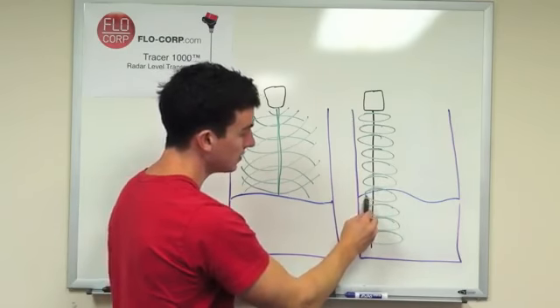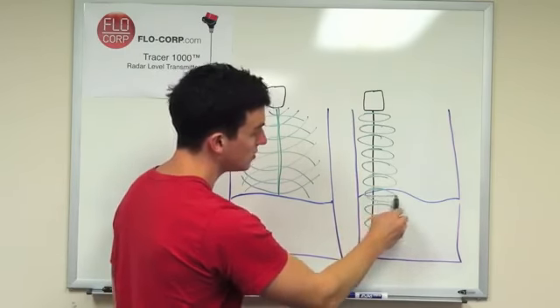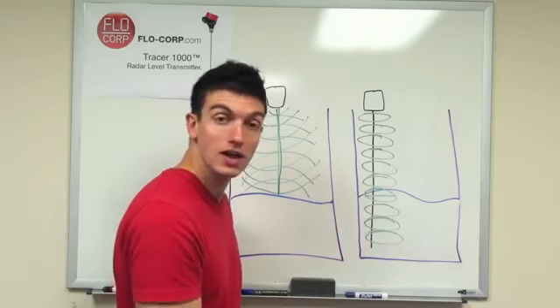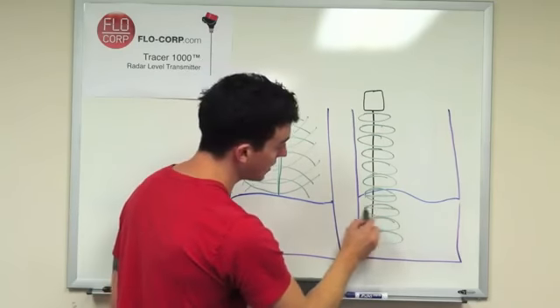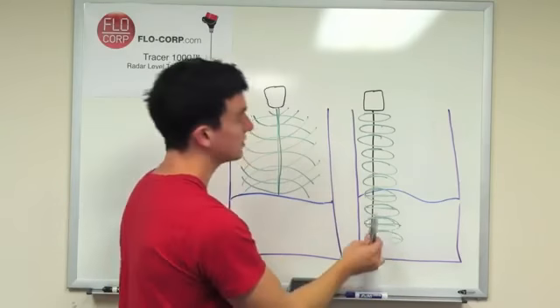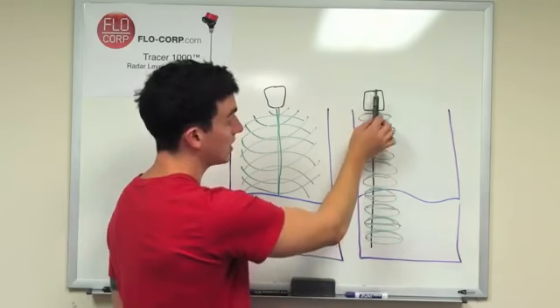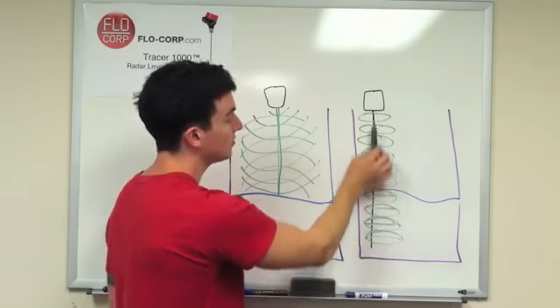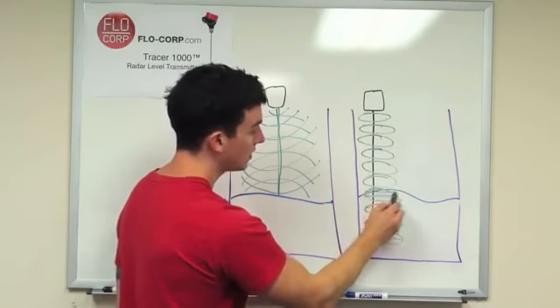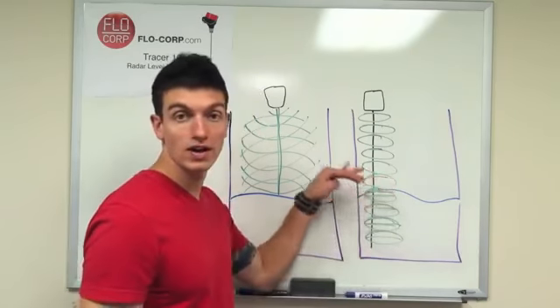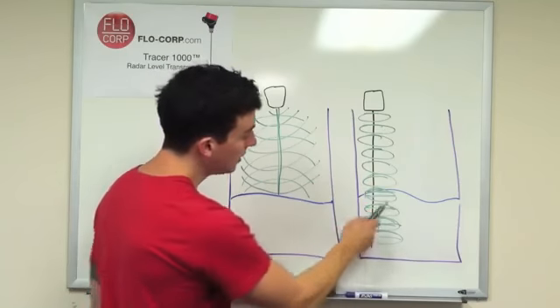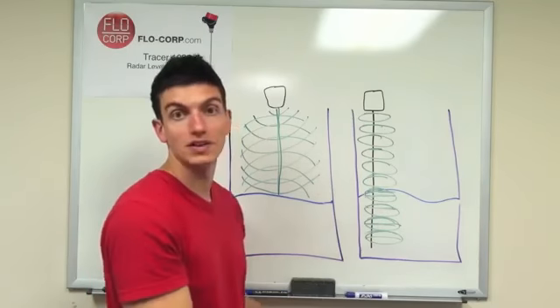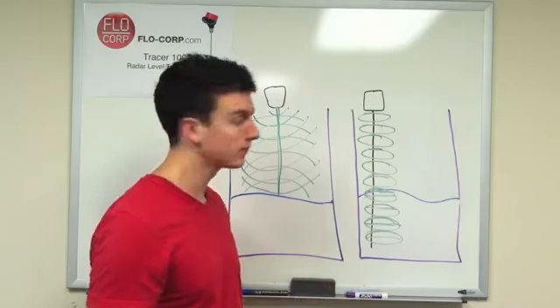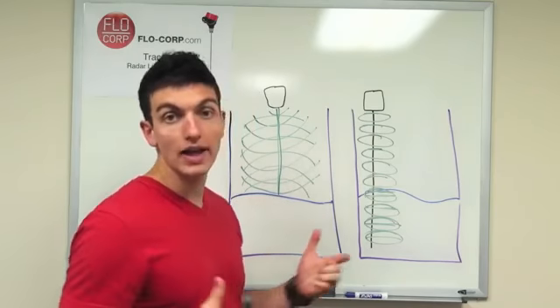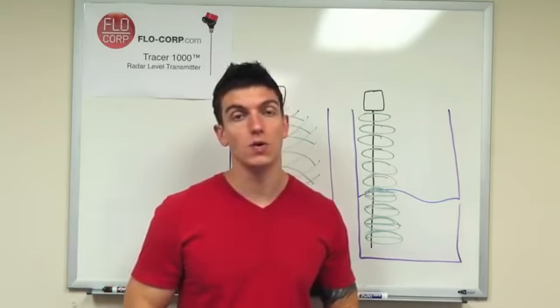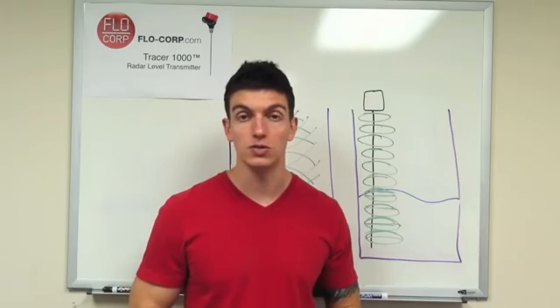When it finally gets into the liquid here, it will take a measurement and continue to do that. And so the artificial intelligence in the meter up here, when it receives this return signal, will know that this is the liquid measurement because it's where it first got a good full signal, and then it confirmed that there isn't a greater signal anywhere below it. So actually both of these meters will work pretty well in this situation.